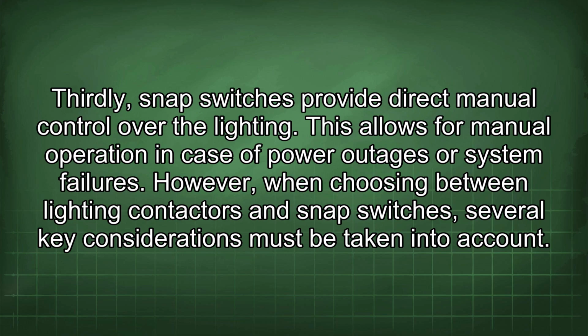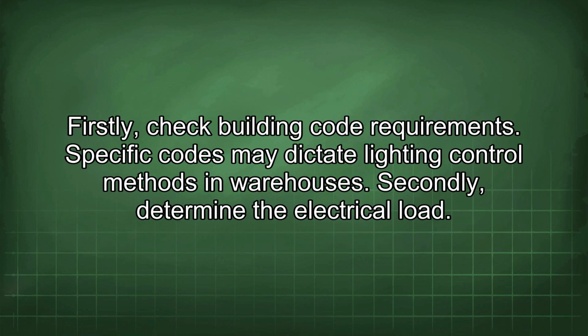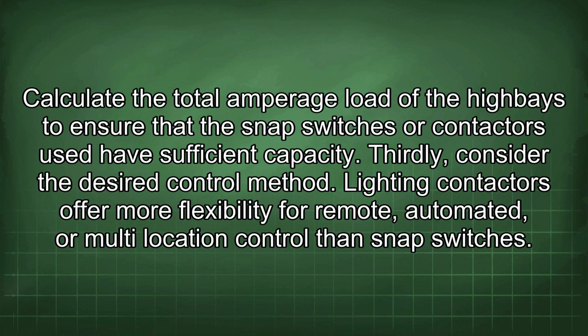However, when choosing between lighting contactors and snap switches, several key considerations must be taken into account. Firstly, check building code requirements. Specific codes may dictate lighting control methods in warehouses. Secondly, determine the electrical load. Calculate the total amperage load of the highbays to ensure that the snap switches or contactors used have sufficient capacity. Thirdly, consider the desired control method. Lighting contactors offer more flexibility for remote, automated, or multi-location control than snap switches.